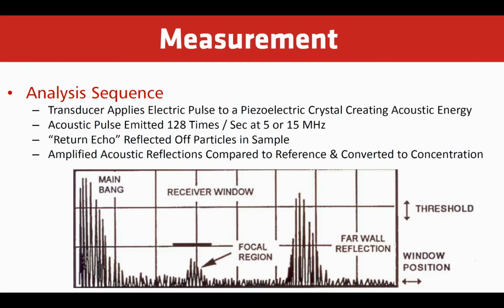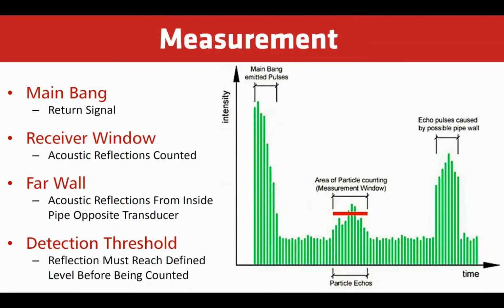Here we look at just an example of the main bang pulse being emitted, the echo return, the particles that echo them in the measurement window, and also, as we see on the other side to the right, is the main bang echo being reflected from the actual sample or the piping back wall. So when we install these, we want to be careful to at least have a minimum of 3-inch piping so that the echo created from the far wall does not interfere with the measurement window echo section.